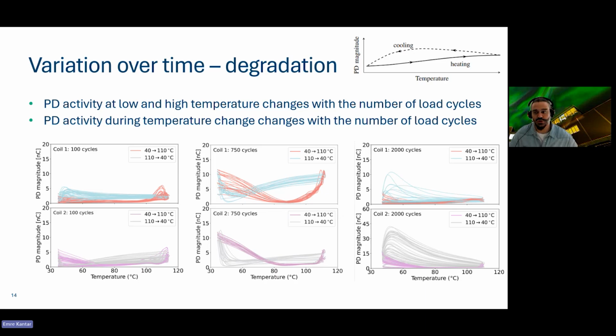To show the entire picture of the degradation based on PD magnitude versus temperature, what we see is some unique hysteresis effects. How this can be summarized is that at the same temperature, we see different PD magnitudes depending on the temperature trajectory, whether heating or cooling. This means the thermal coefficients of the insulation and copper are behaving differently from heating to cooling. So although the same exact temperature was achieved, PD characteristics followed different trajectories. I won't go into details now, but we have a paper explaining all the possible mechanisms, so I'm not going to bore you with the details here.